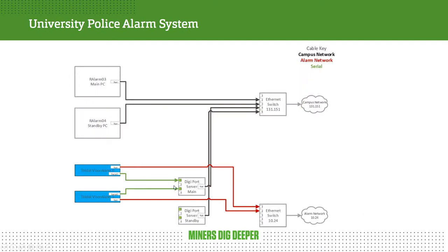And so again, here is the manual failover portion. In other words, if this guy were to die, then you basically have to take this cable connected to port 1 of this, take this cable connected to port 3 of this, and all things being equal, the alarm PC should stop complaining, and then everything should continue to work.